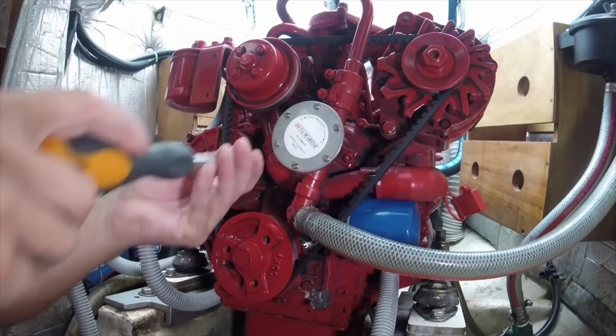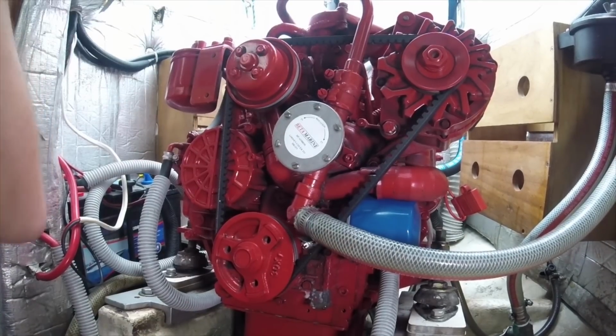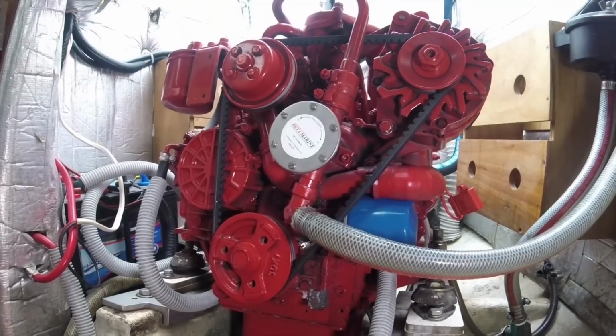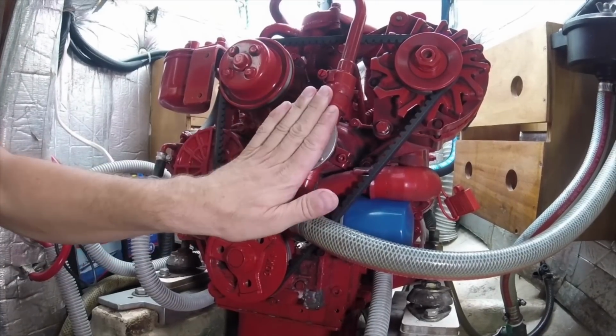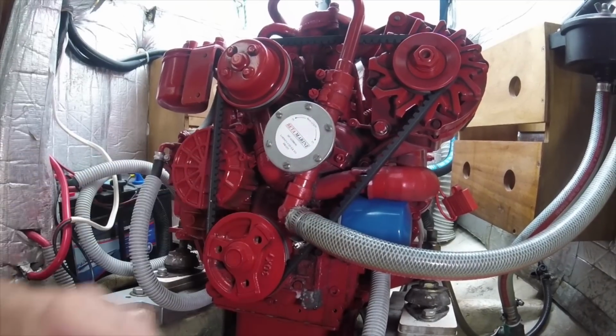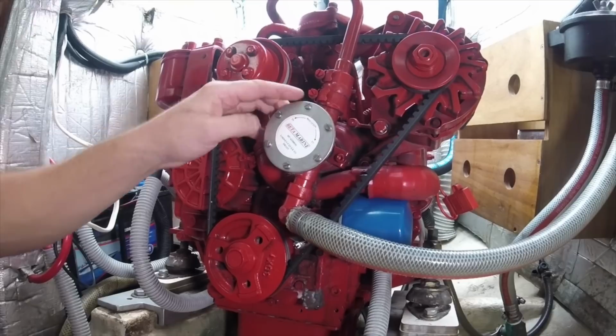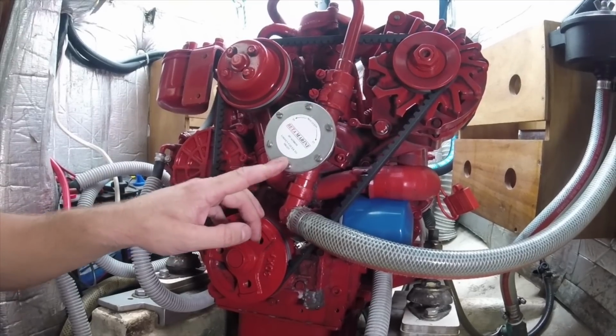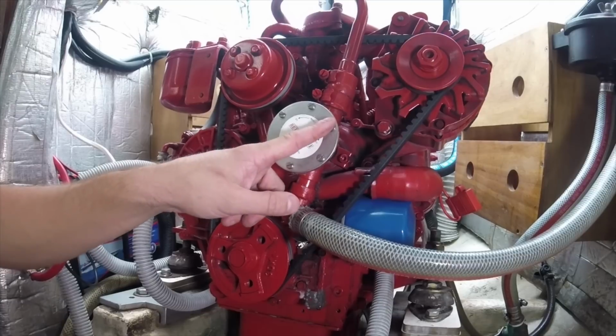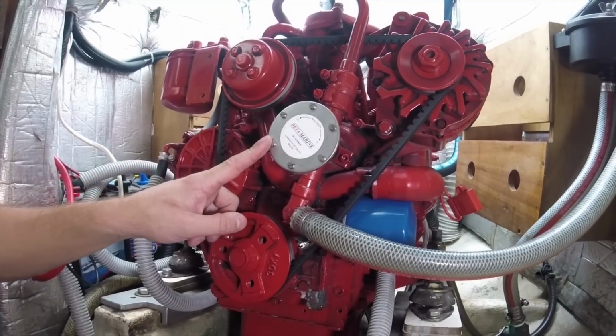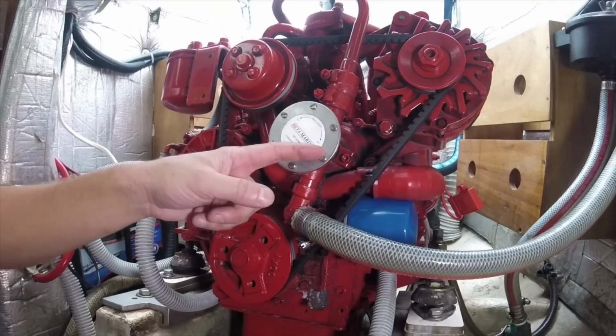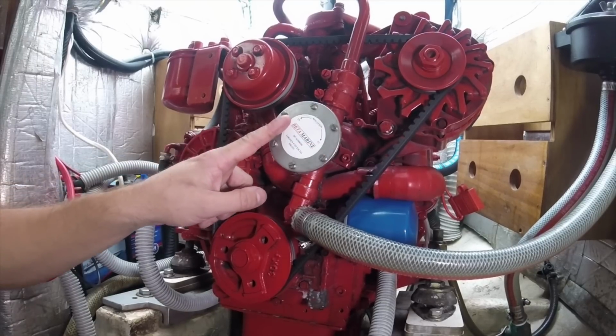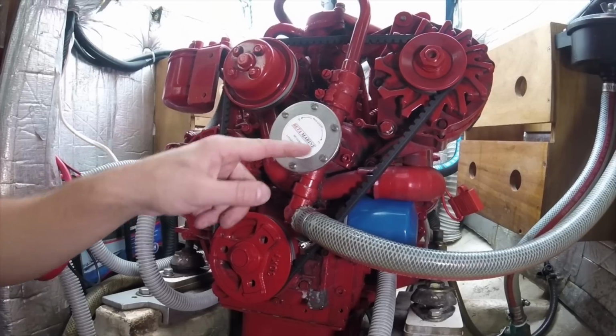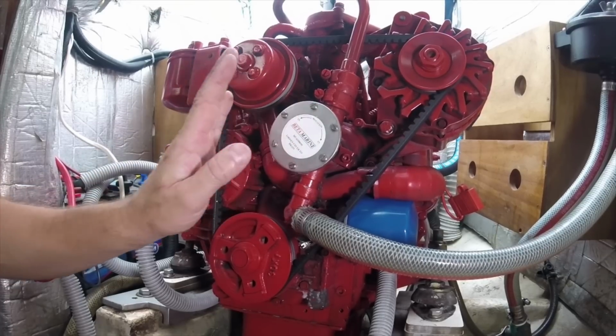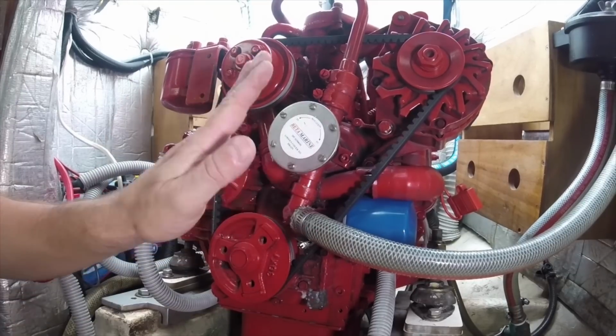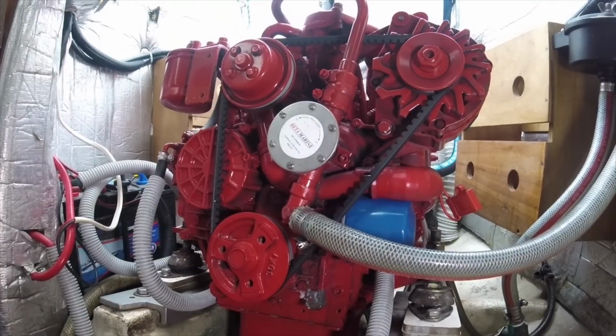The next thing we need to do is tighten these up in a manner that pulls the cap down evenly onto the flange. We do that by starting at 12 o'clock, coming down to 6 o'clock, then up to 2 o'clock, across to 7 o'clock, then to 5 o'clock, then up to 11 o'clock. I'll do that a couple of times, gradually and evenly tightening the cap down onto the flange of the pump.